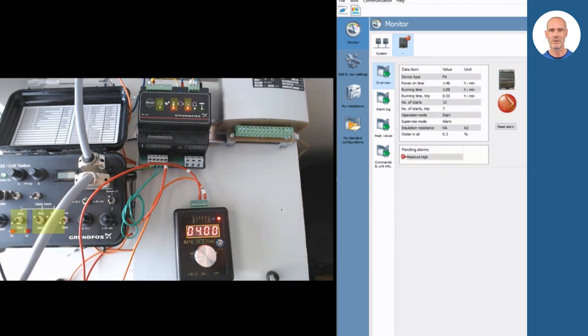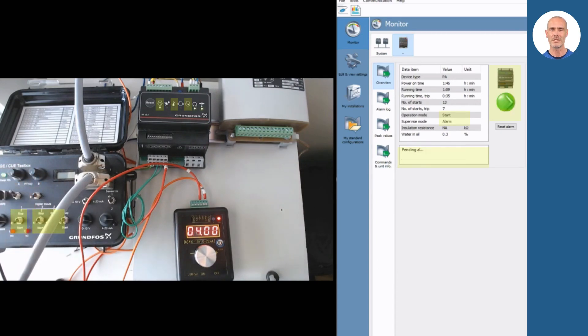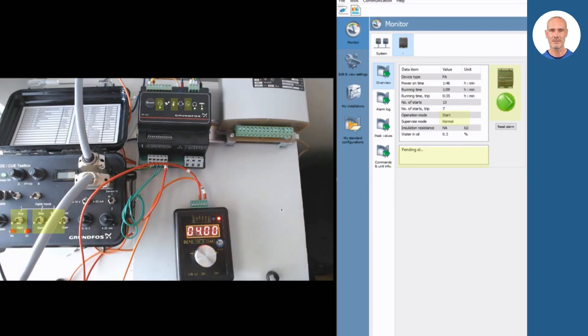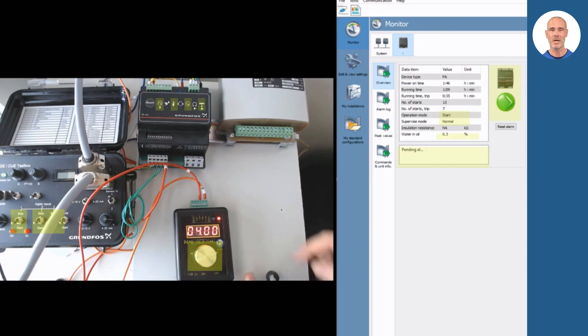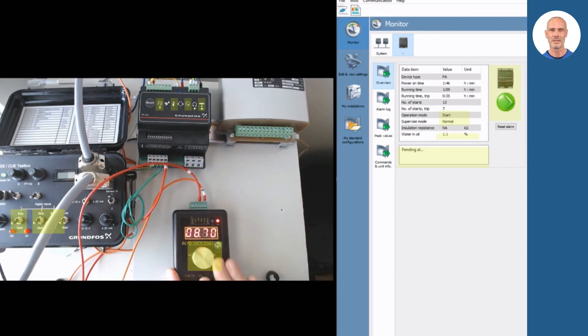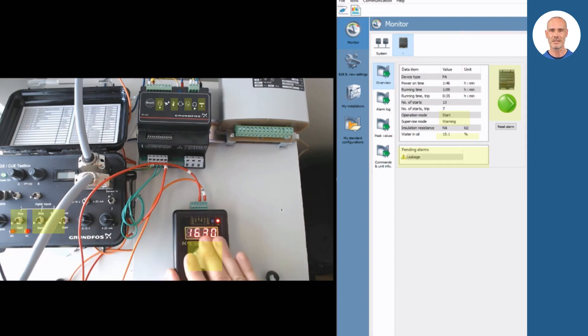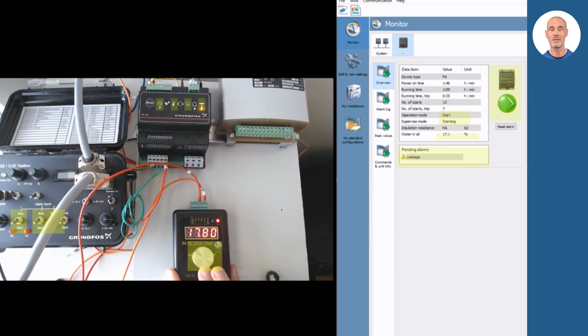After it, we activate the moisture switch. As a result you can see the alarm LEDs activated. We reset to clean the alarms and to follow simulating the water in oil sensor. Once the measurements reach different values, the system will show different blinking LED sequences to warn about water concentration in oil.